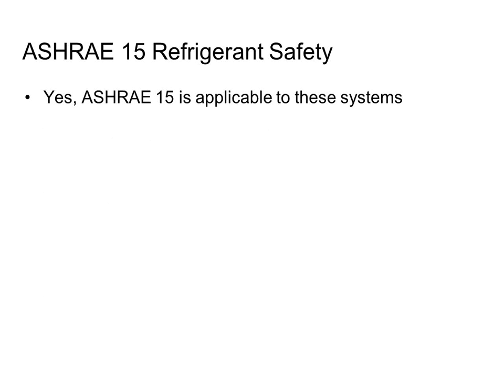So the first question is, yes, ASHRAE 15 does apply to VRF systems. I can't tell you how many people I've heard say, no, VRF has an exception because it would be impossible to do it. One, there is no exception for refrigerant safety. It's a safety code. There's no exception, right? You have to do the safety code. Two, I don't know why you would say that because there's multiple zones we don't have to do it. It's even more critical that I pay attention to it on these systems. So yes, you have to follow ASHRAE 15 or your applicable local refrigeration code like in the city of Chicago.